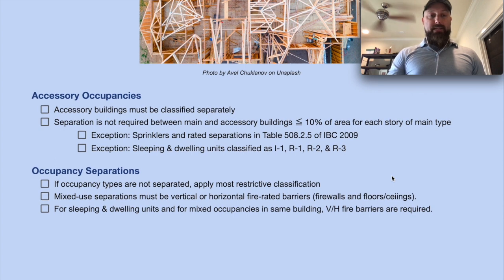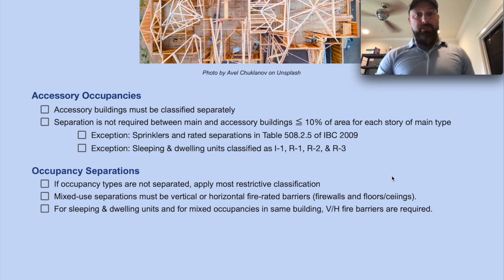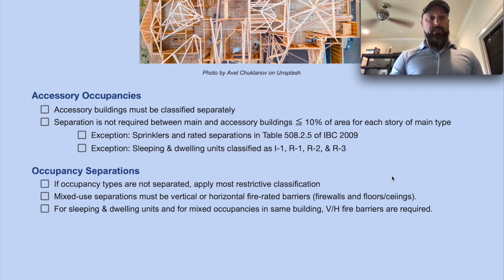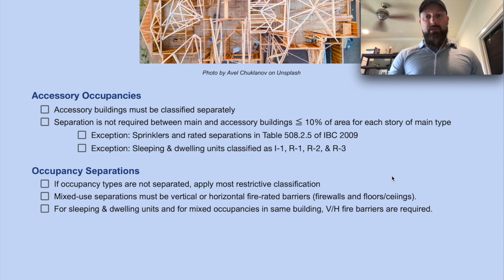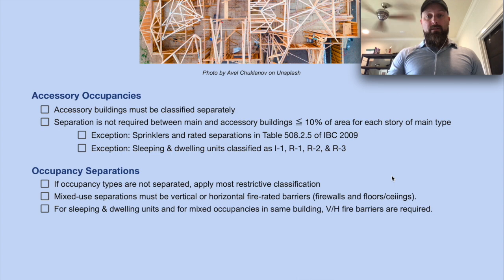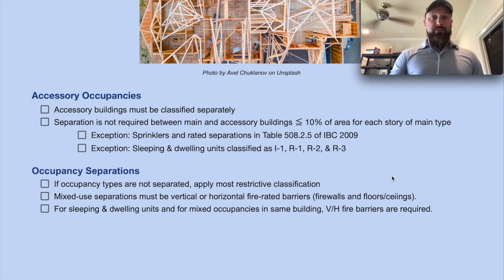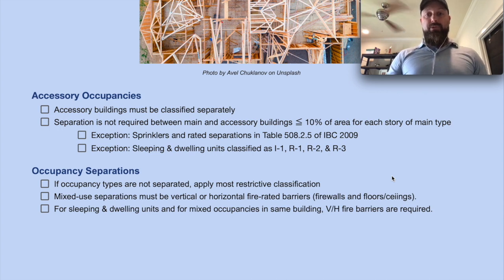For accessory occupancies, accessory buildings must be classified separately. Separation, however, is not required between main and accessory buildings if it's less than or equal to 10% of the area of each story of the main type or classification. The exception is sprinklers and rated separations — that's in table 508.2.5 of IBC 2009.